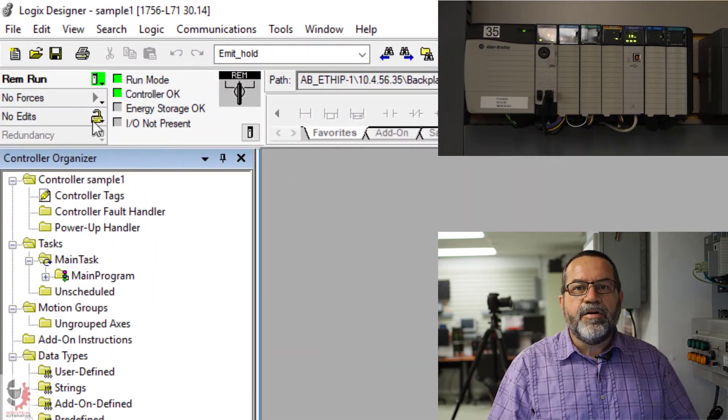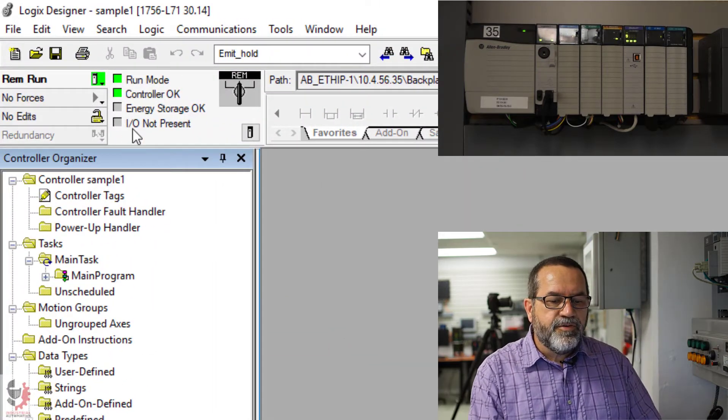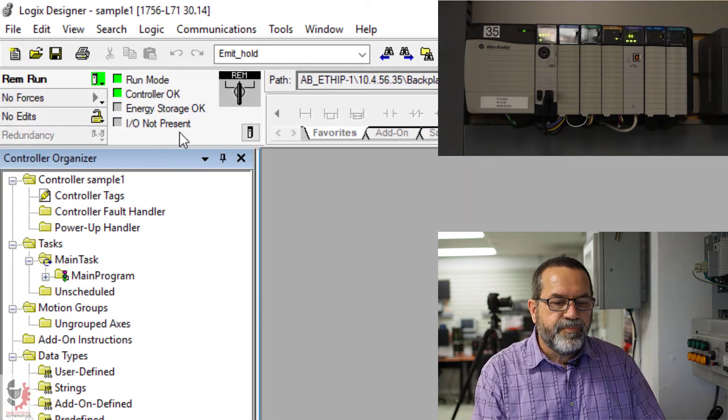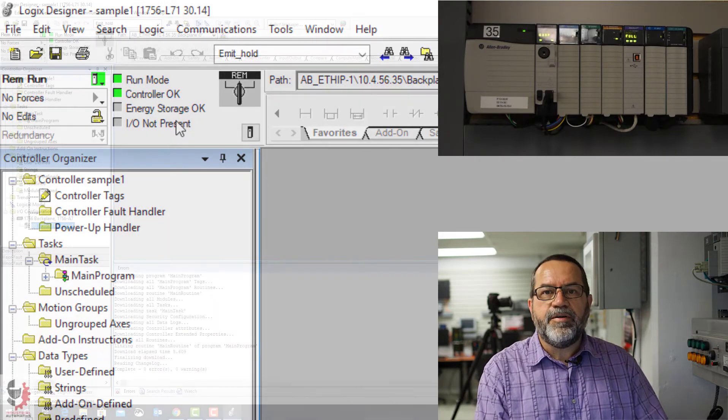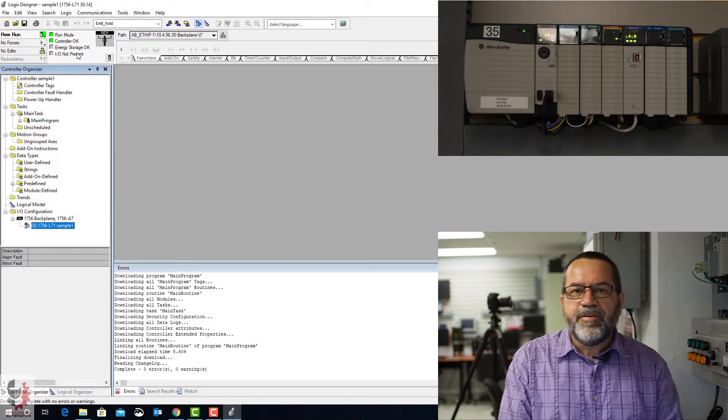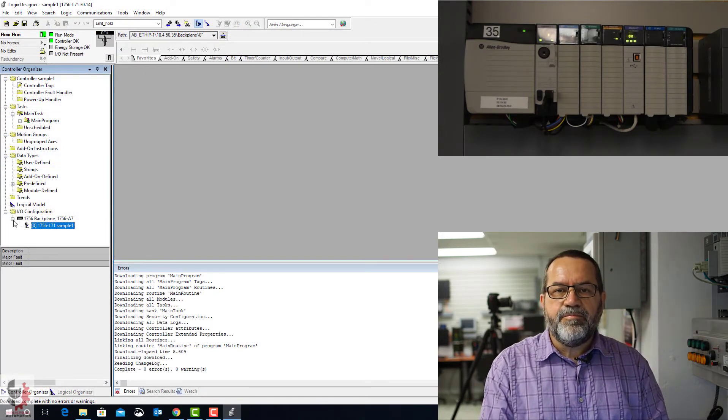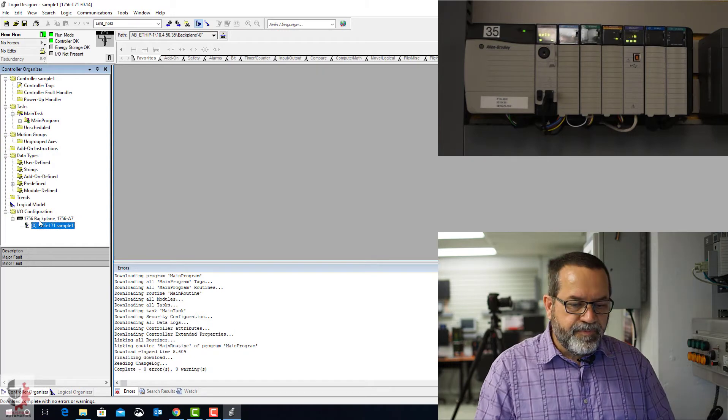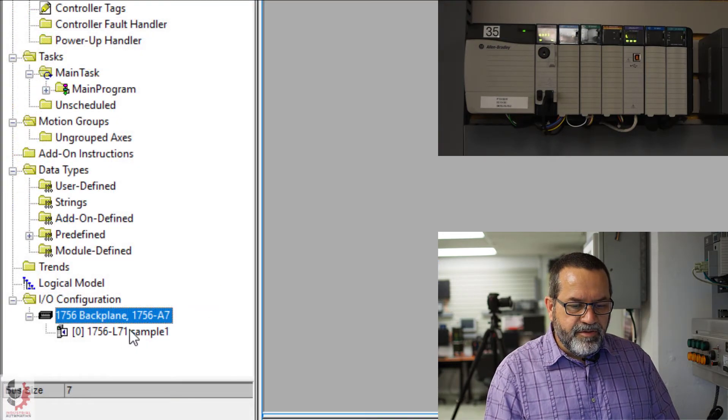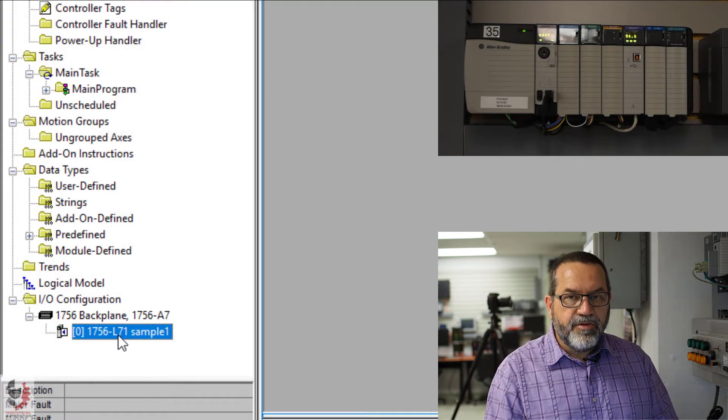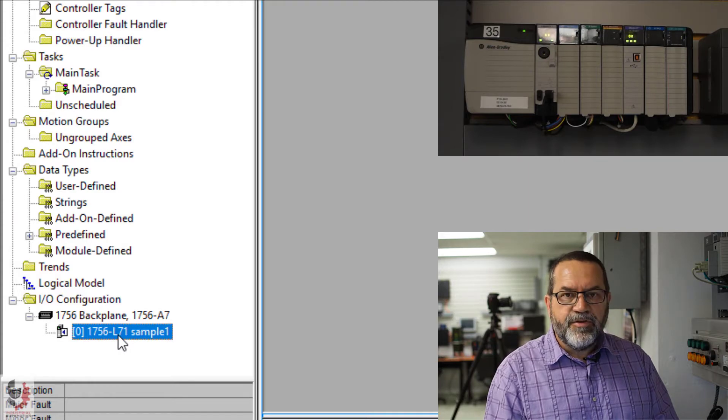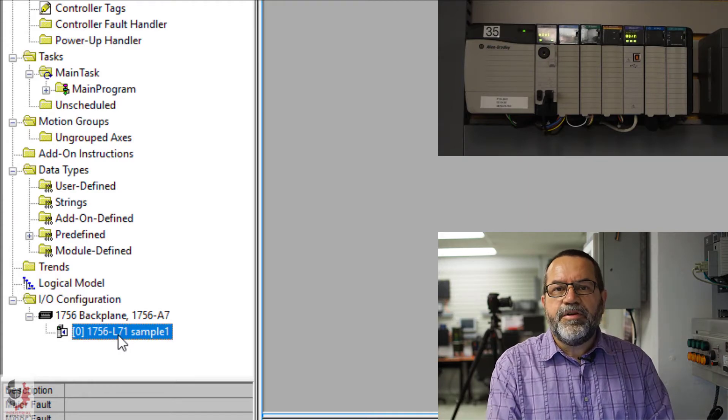All right, so now I'm online. I've got green lights here, but notice it says I/O not present. And that's because I haven't configured any of my modules. If I look down here, I've got... It's showing the backplane, and it's showing the controller, but it's not showing any of those inputs and outputs.